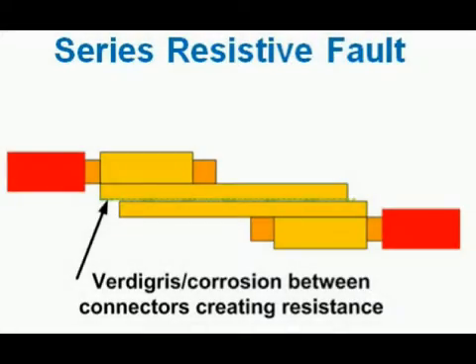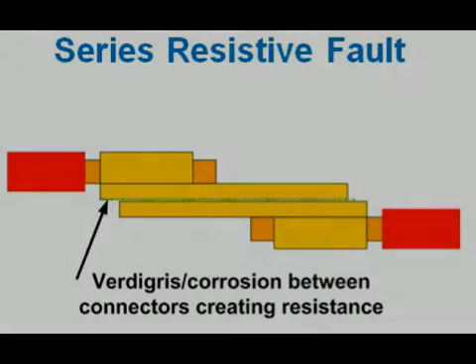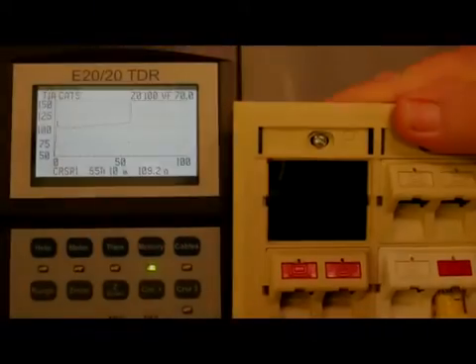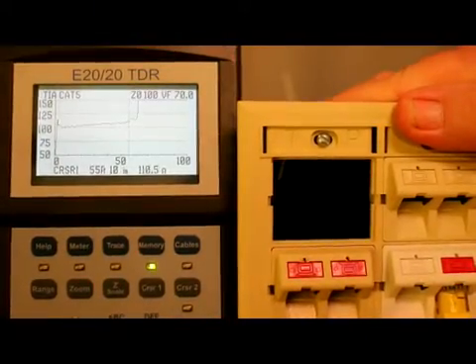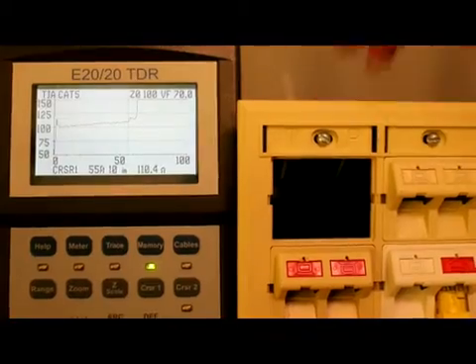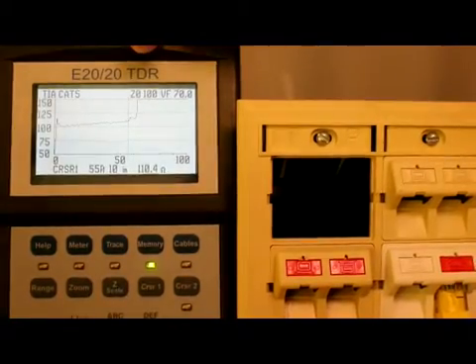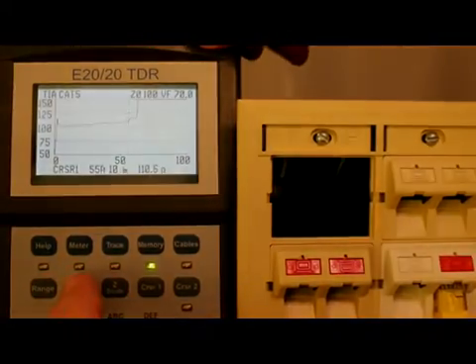Another issue is series-resistance faults. These are generally caused by dirty, contaminated, or corroded connection points that add resistance to one or both conductors in a pair. The result on a STEP TDR is a sharp upward step in the trace — that's the resistance being measured at the fault and added to the impedance. Again, another unwanted reflection and attenuation point along the pair's length that needs correction.